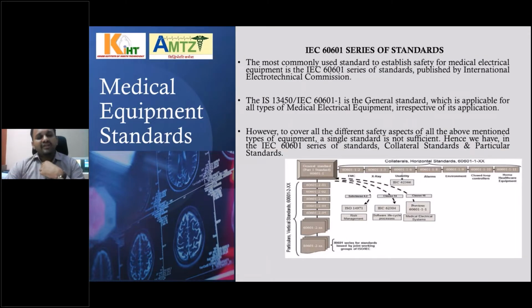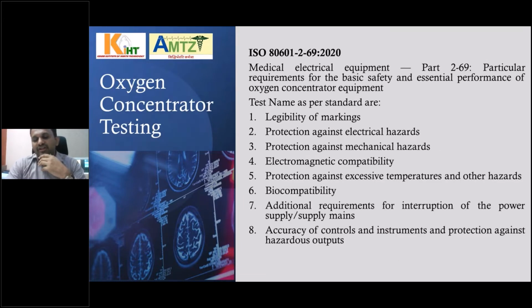If you see the medical equipment standards, there is a series which you might be aware of, shown in my PPT. One is the horizontal standard, which is applicable across categories, for example for radiology 60601-1-3 is applicable; we call it horizontal or collateral. And the particular standard, which we also call a vertical standard, for oxygen concentrators is 80601-2-69. So as today's topic is the oxygen concentrator, the particular standard is 80601-2-69, which gives particular requirements for the basic safety and essential performance of oxygen concentrator equipment.